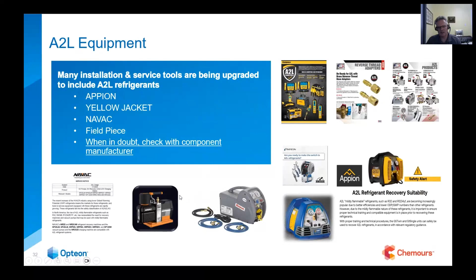Looking at transportation of dangerous goods, I wanted to mention hauling refrigerant in our trucks. Certainly the cylinders with A2Ls need to be upright, and upright means that the pressure relief valve needs to be in the vapor space. So the cylinder can be at an angle, but you certainly cannot have them lying down. There are also 150 kilogram and 500 kilogram exemptions in transportation of dangerous goods, which allow us to transport refrigerants without placards. So those are in place.